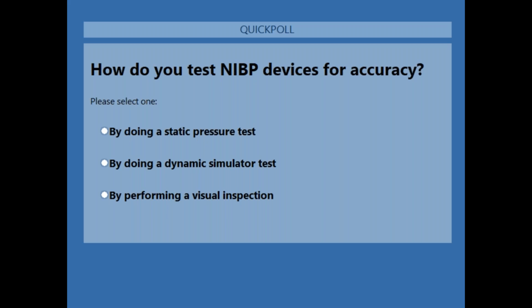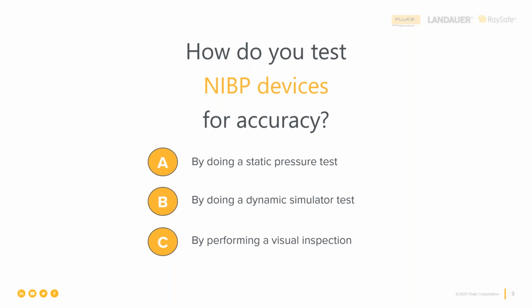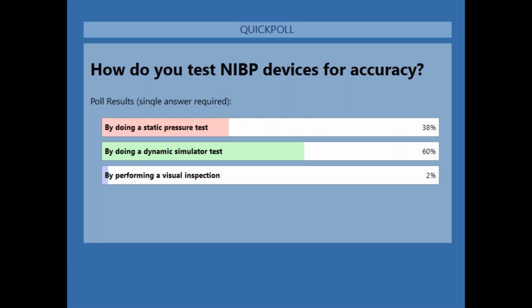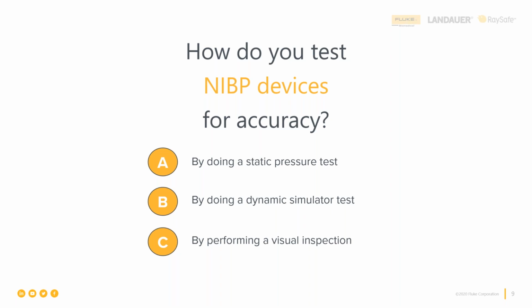Okay, numbers are climbing. Okay, Jerry, I will close the poll and show. So we have 38% by doing a static pressure test, 60% by doing a dynamic simulator test, and 2% by performing a visual inspection. Very good. Well, so very interesting and also very not unusual for the many times that we've gone through and are providing training about NIBP accuracy and measurement for patient monitor testing around the world over the last several years.